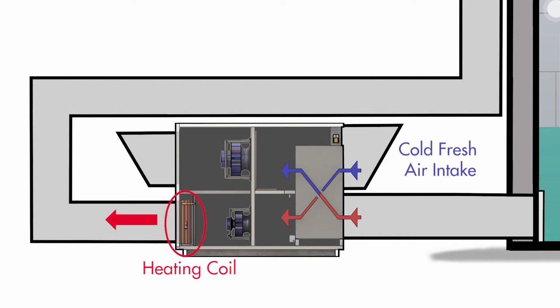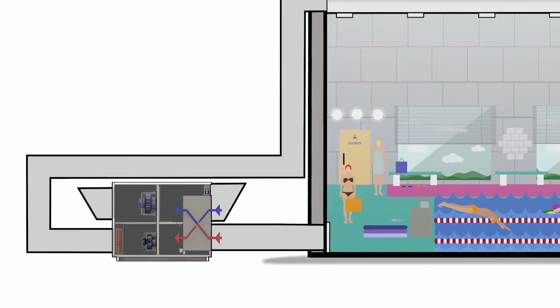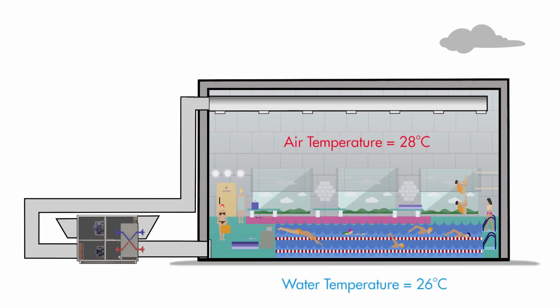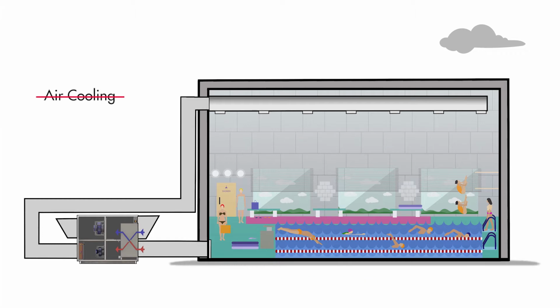The supply air then needs to be cooled or heated further by a separate system to maintain the desired room temperature. Generally, heating is more critical for indoor pools, as the air temperature should be kept close to the water temperature to ensure user comfort and to minimise heat loss from the pool water. Often, air cooling equipment is considered unnecessary for indoor pools.